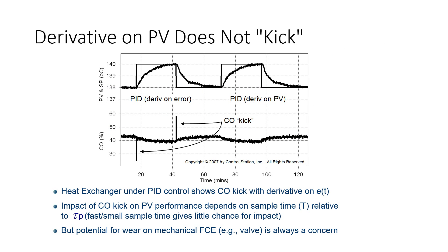With derivative on error, each set point change causes a derivative kick — the controller sees a sudden large error change. When using derivative on PV instead, there is no kick at those points, and the control response is nearly identical. The kick doesn't affect operations dramatically since it only lasts one cycle, but eliminating it is beneficial — you don't want a valve opening and shutting very rapidly if you can avoid it.